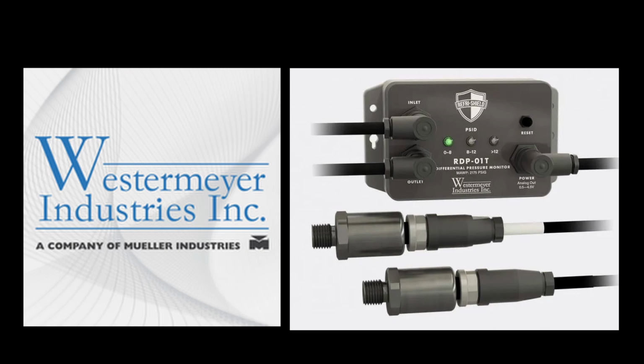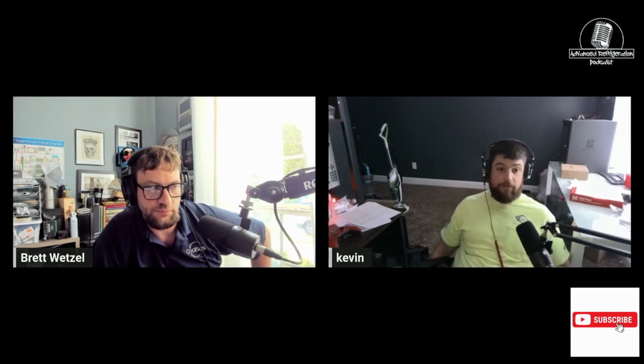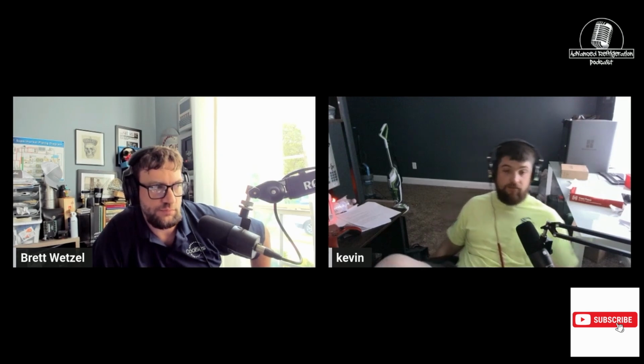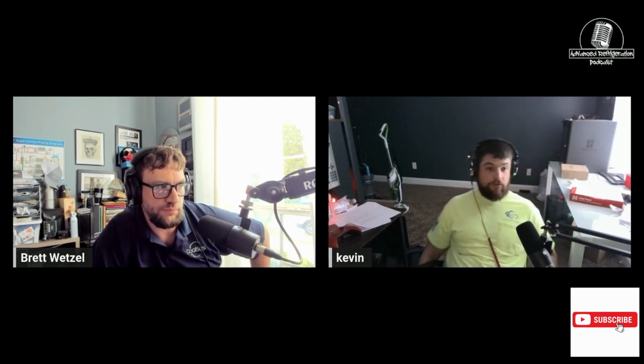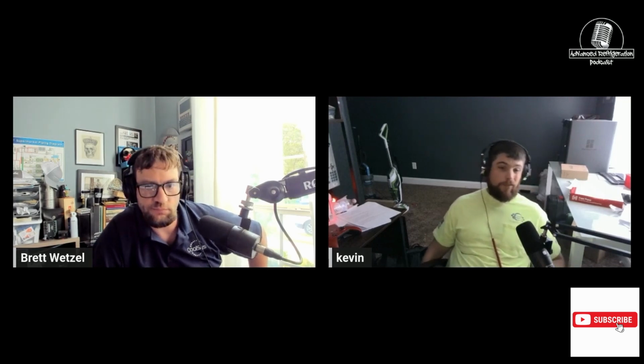Yeah, they do. But you're right, they have balancing valves on them. The Walmarts have balancing valves. The Zero Zone design for Costco is no balancing valves, and the older design was a bypass valve around supply to return at the pump station. So they would use differential to bypass supply to return, which somewhat works, but you don't get the efficiency gain from having the VFDs.